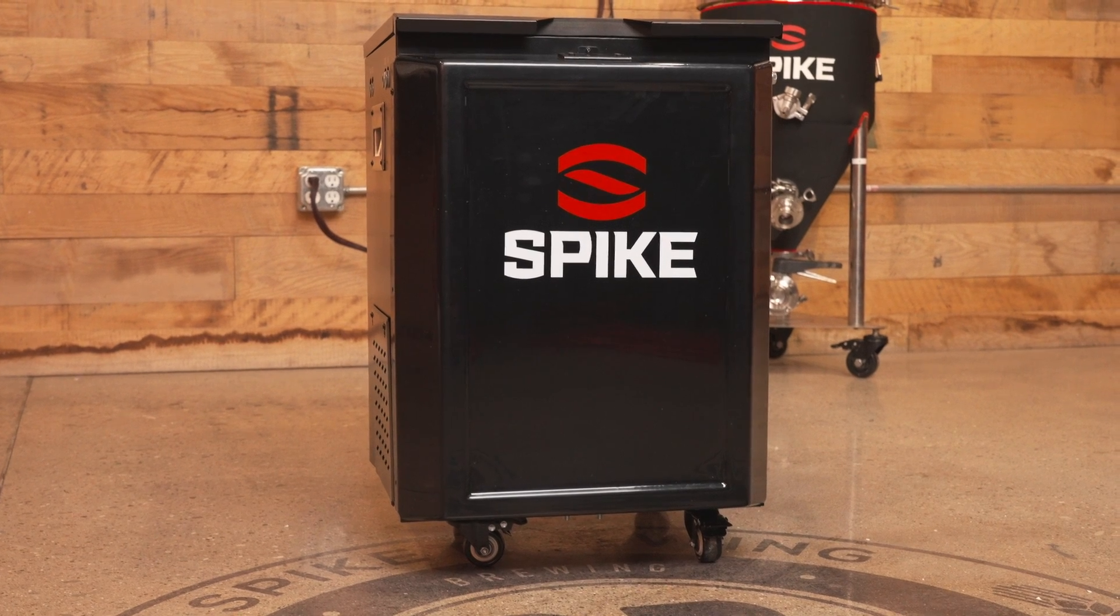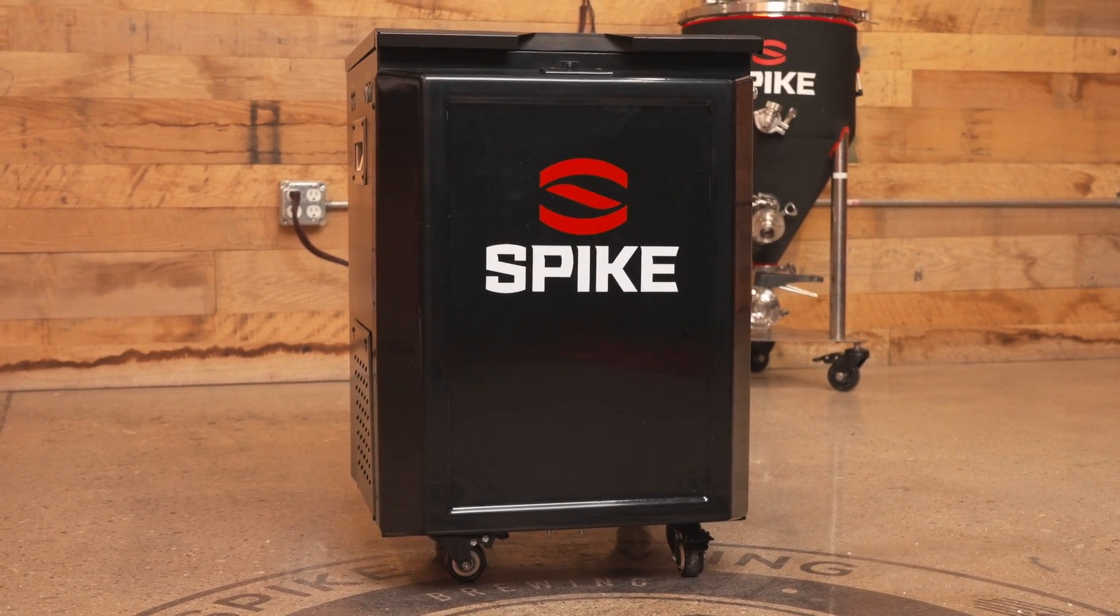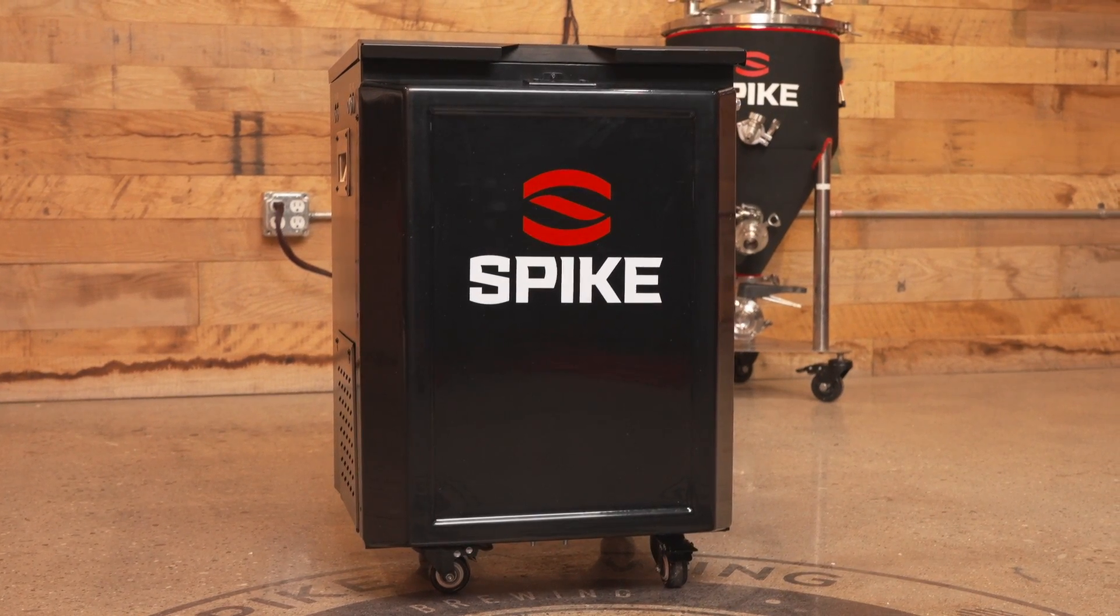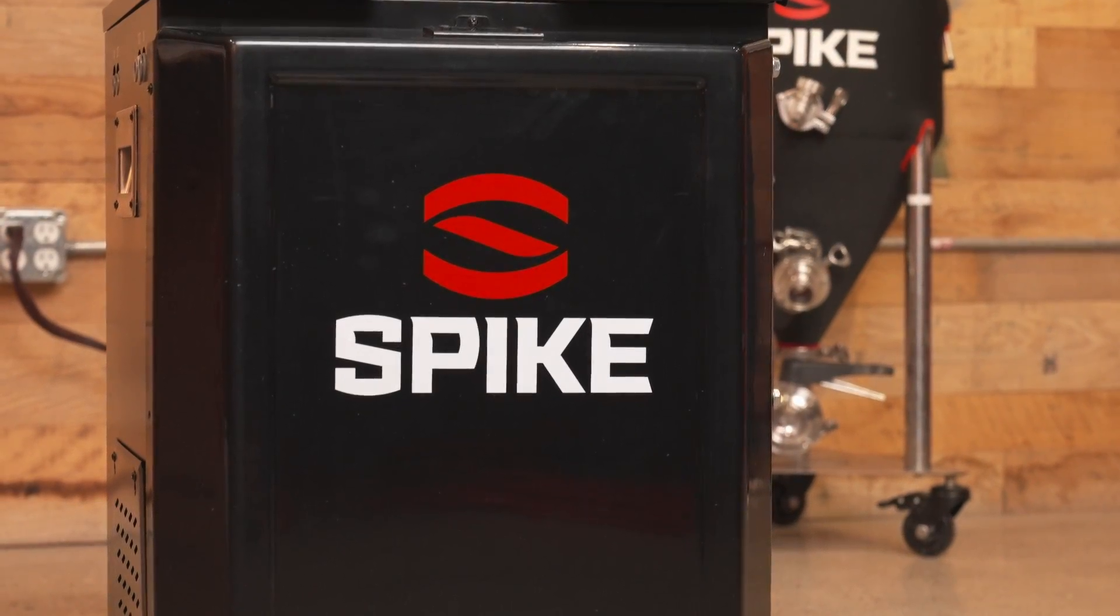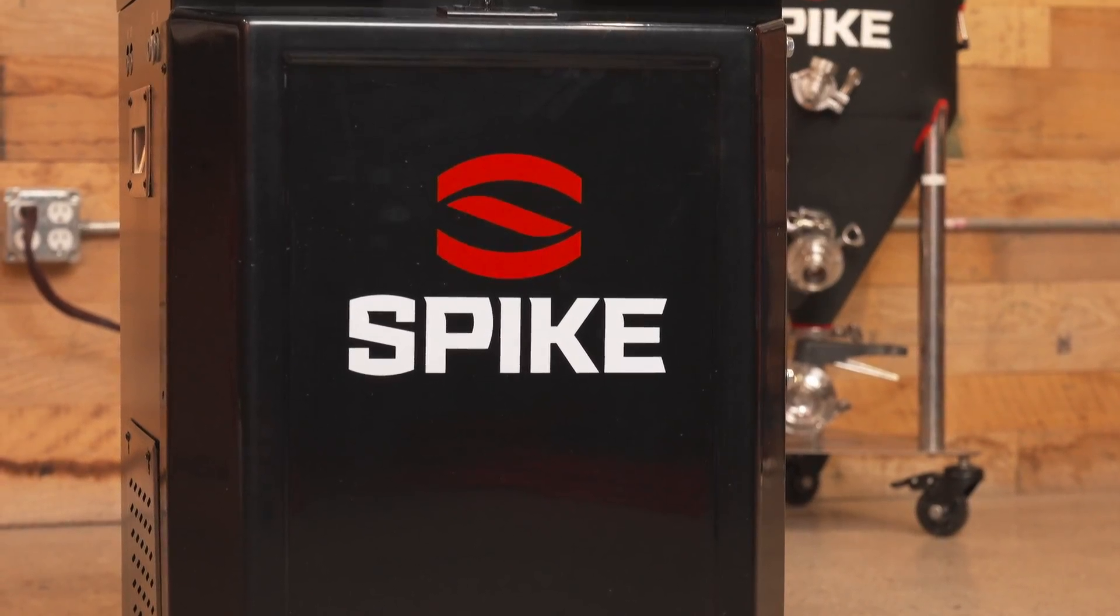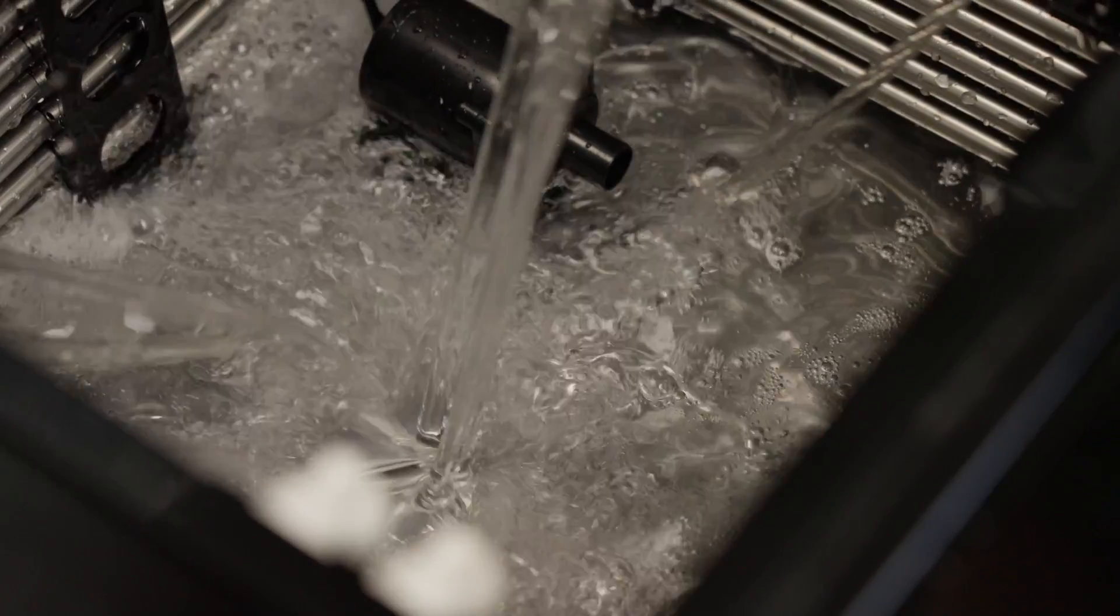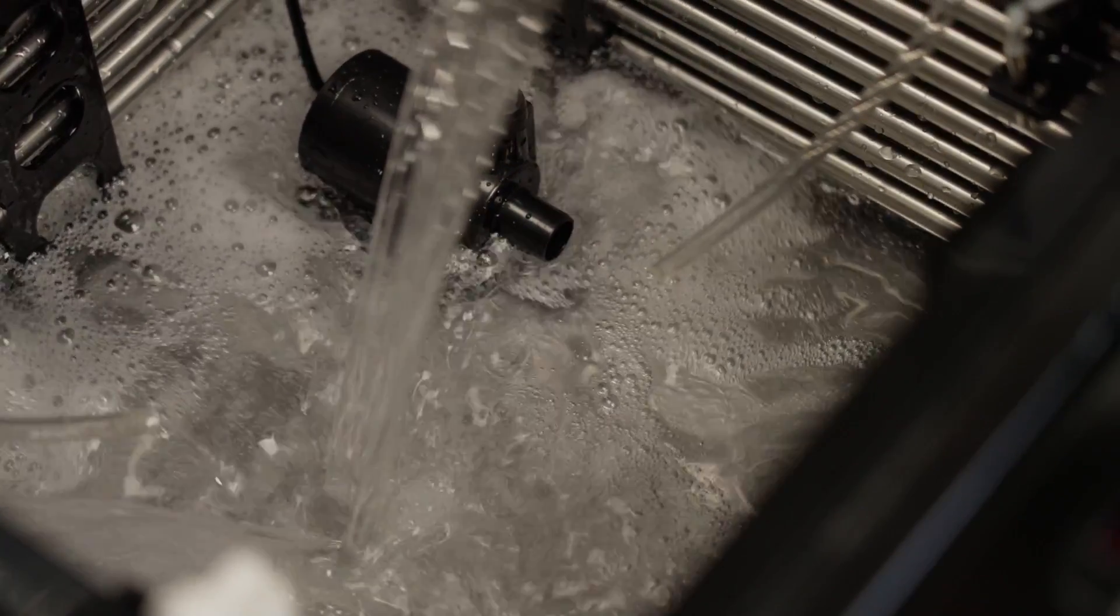Pro tip, a distilled water to glycol ratio is a two to one ratio, two parts distilled water to one part glycol. Fill the tank until the coils are submerged with a two to one distilled water to glycol mix.